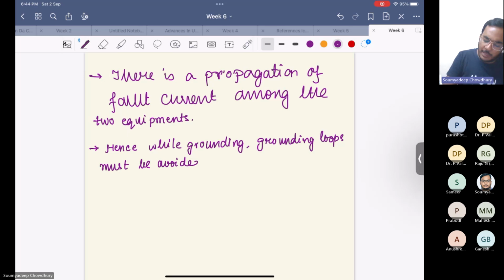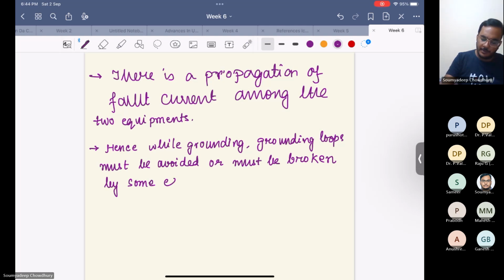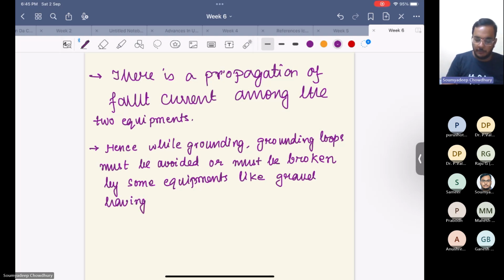How will you avoid these grounding loops? You have to break these loops by using materials of very high resistivity, in the soil only, like gravel having very high resistance. So if you give a very high resistance in between, this fault current will not propagate to the other equipment.